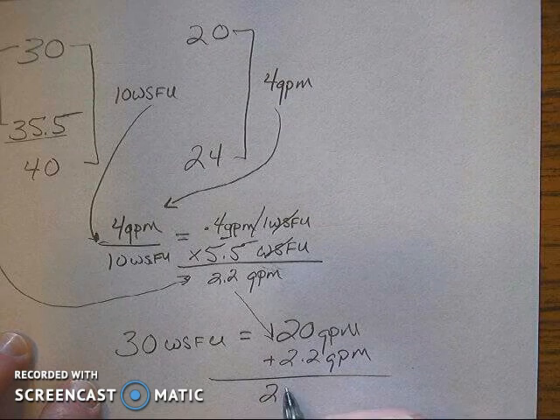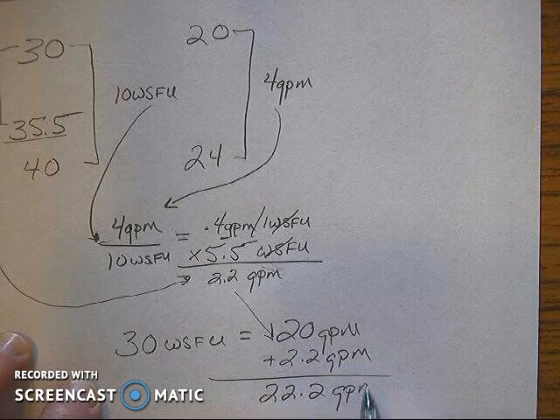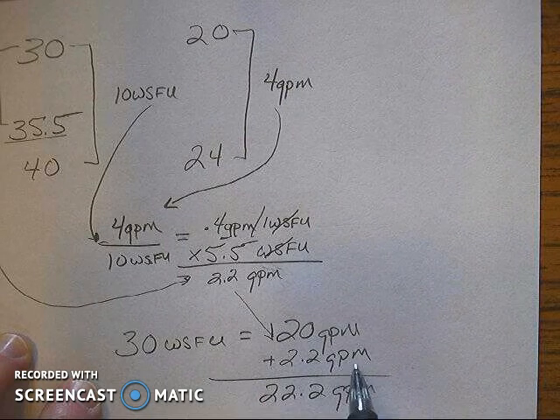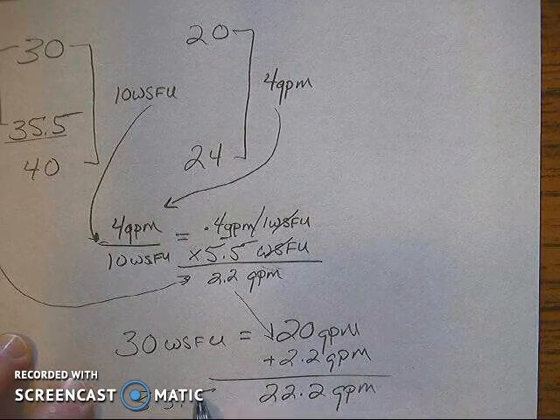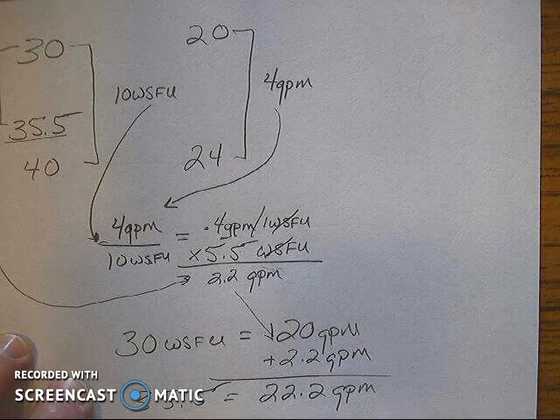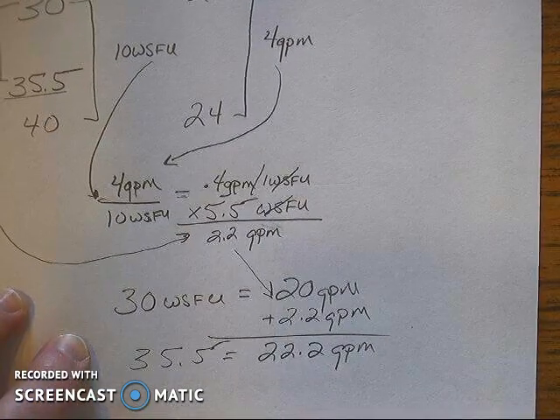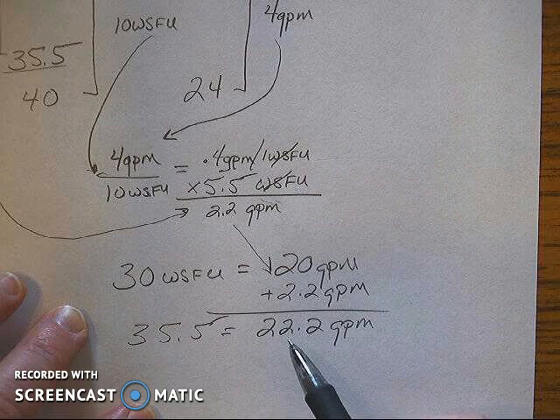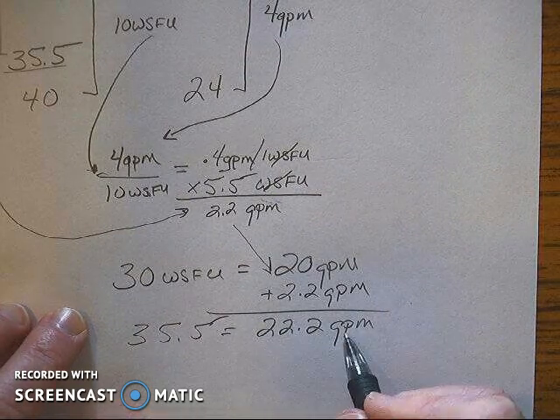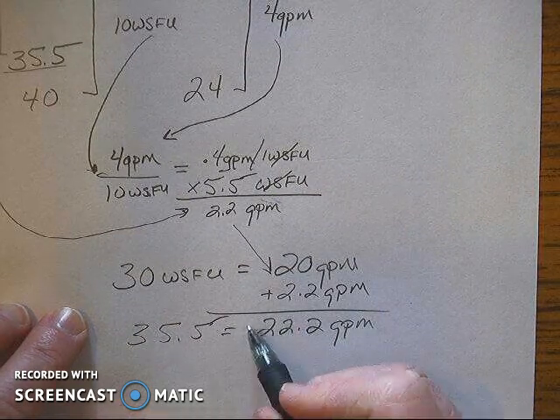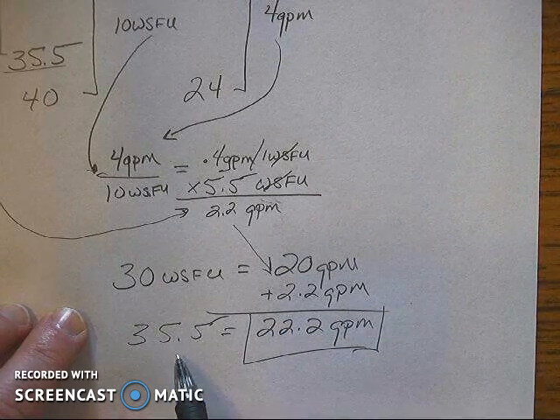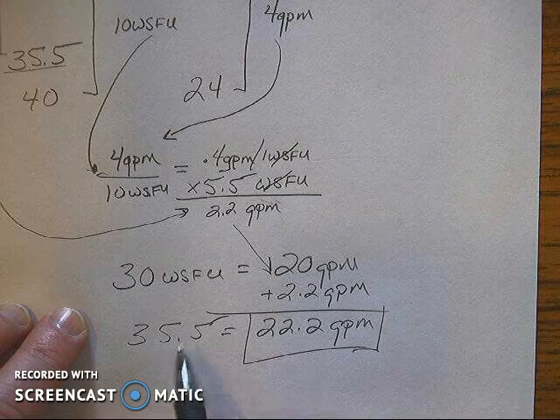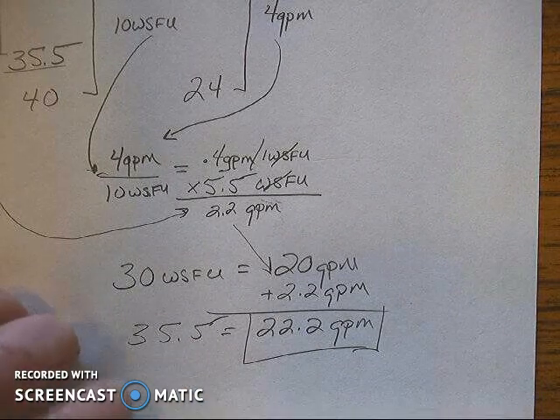And that's going to bring us up to 22.2 GPM. So 35.5 WSFU equals 22.2 GPM. 22.2 GPM is the equivalence of 35.5 flush tank WSFU.